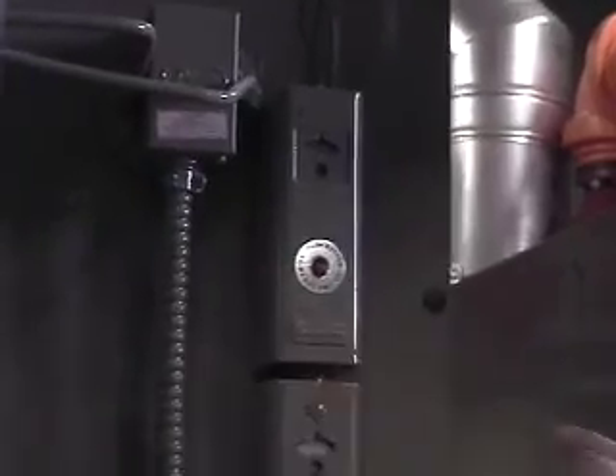So we've got this set to 180, and then we've got this set to just over 200. So it's about 200, it's right at 200. So if this fails, then this guy will trip the boiler off, and that's where you get the nuisance call. The boiler's in alarm. I can't get it to fire. This would be the reset button that you push, and if it clicks, then you know that it tripped on that. So you check the temperature. You know that it failed for a reason. Something's wrong here, something's wrong here. If you keep getting nuisance calls, check the difference between these two. They might be too close, so they may have adjusted that. Again, if you have a 5-degree difference, if this shut the boiler off, the boiler could keep heating up and keep tripping on this guy over here. Okay.